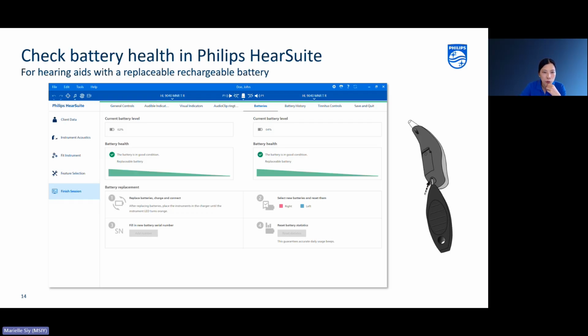And then step 4 is to reset the battery statistics. This is currently grayed out in step 4, but normally that's colored. And when you click on that, it makes sure that the HearLink 2 app will have an accurate battery level readout. So maybe in the first day, it might not be super accurate, but in the following days, it should be more and more accurate to read out the battery level of the hearing aid.